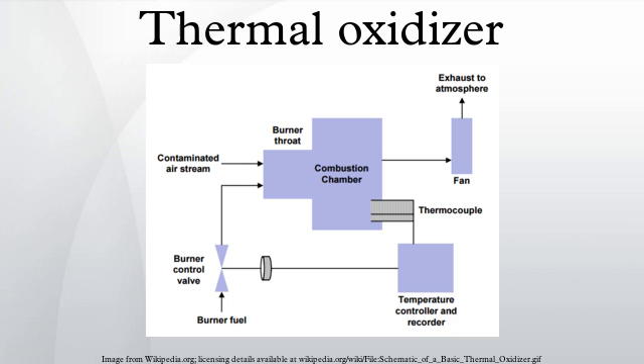Three main factors in designing effective thermal oxidizers are temperature, residence time, and turbulence. The temperature needs to be high enough to ignite the waste gas. Most organic compounds ignite at temperatures between 590 degrees Celsius and 650 degrees Celsius.